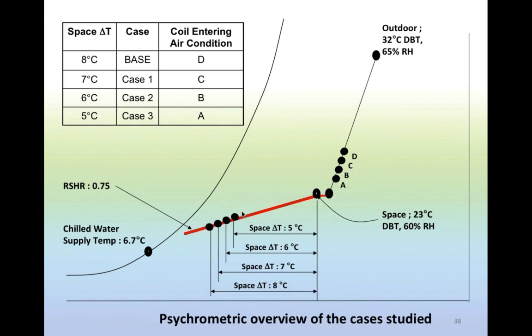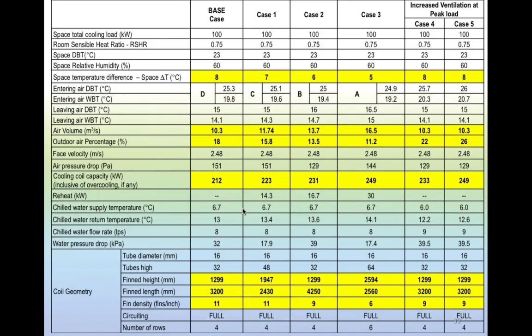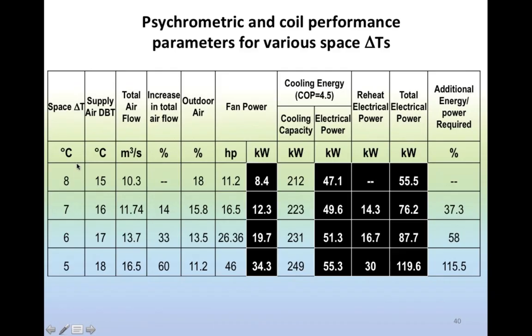So the further away you are from the saturation line, the more challenging it is and the more energy penalty you would incur. Again, I'm not even bothering to look at this slide in any detail. All I would like to highlight, when you see this later in the handout, you can look at the specifics of it. I have the base case, the 3 cases here, and also another situation where I'm increasing the ventilation requirements. What's the consequence of it? When we look at the implication, 8 degrees delta T, that's my base. I started with that as the base case.